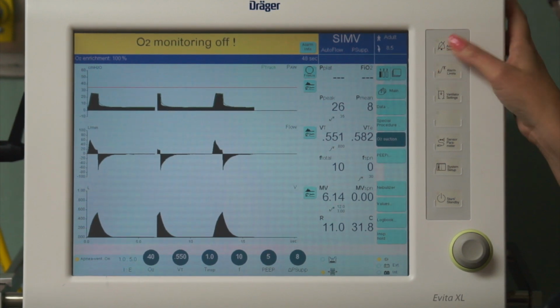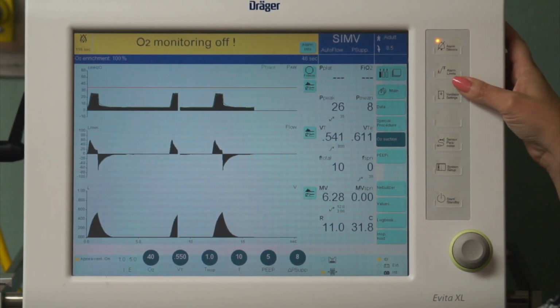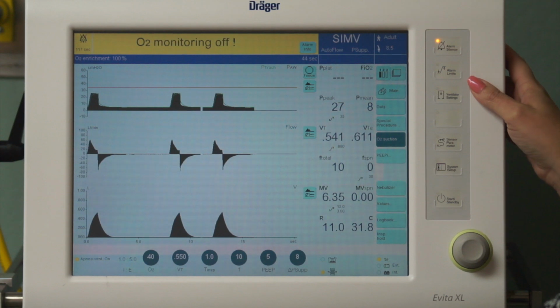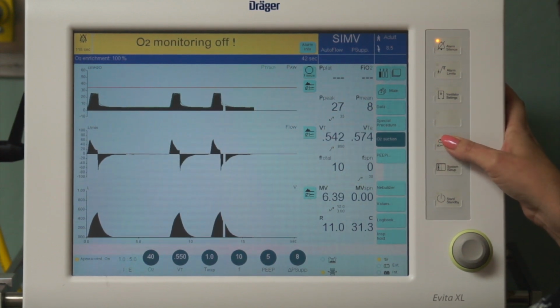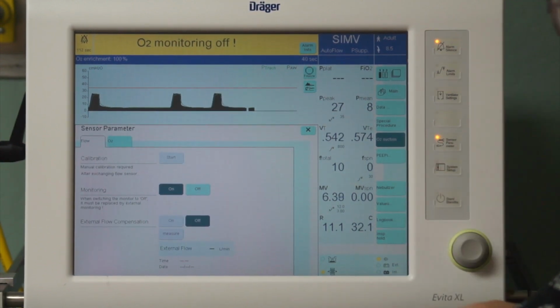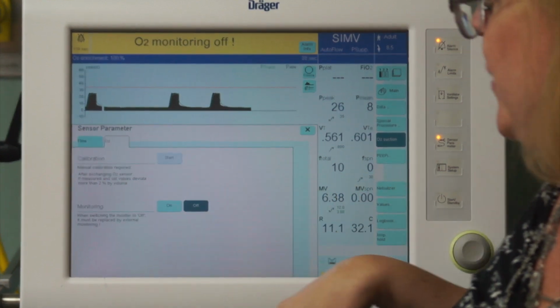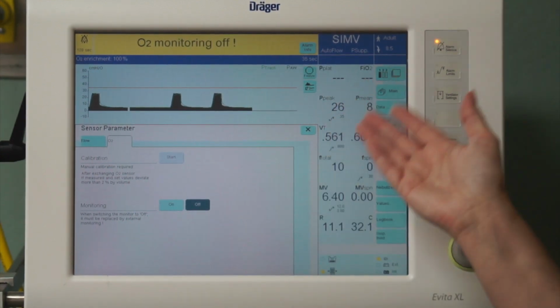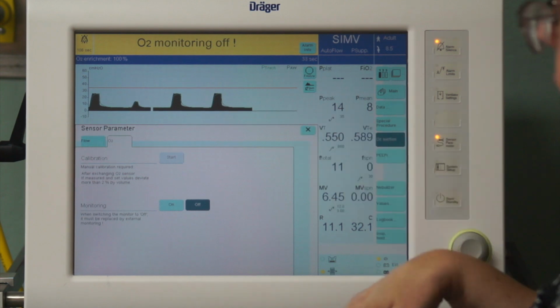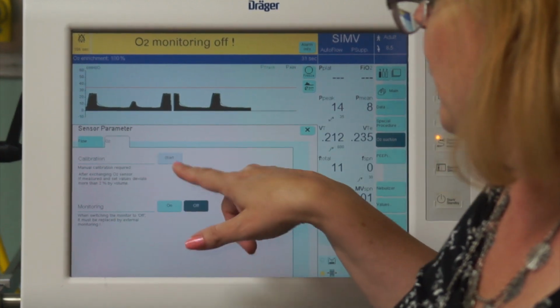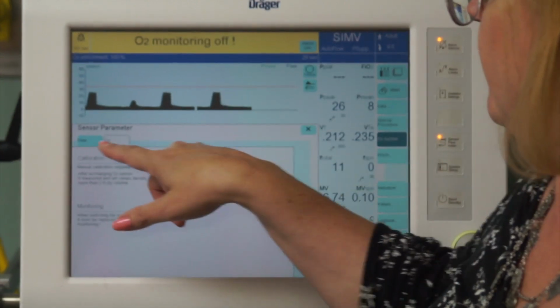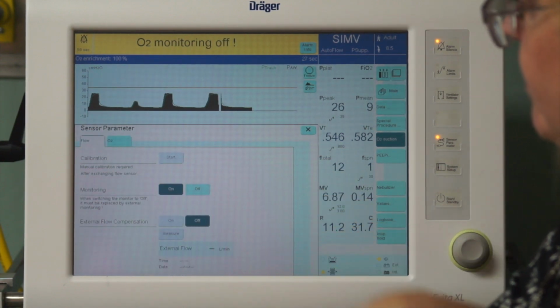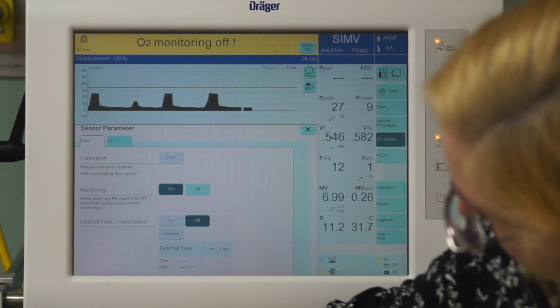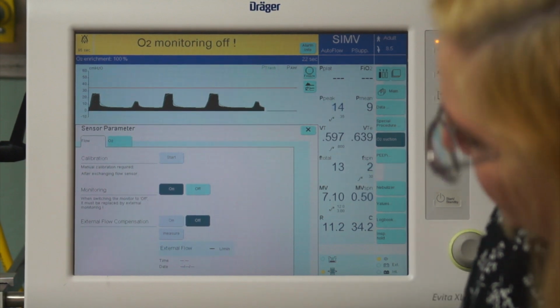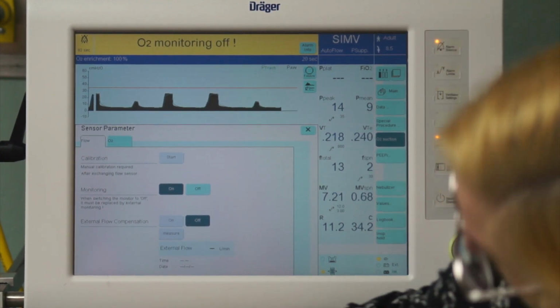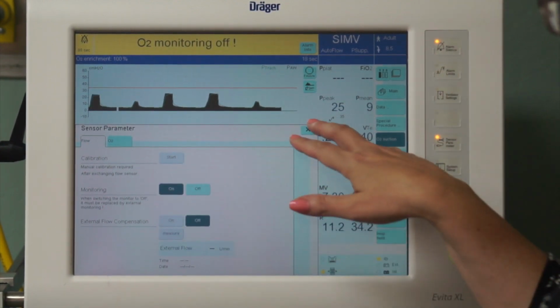So, alarm limits we went over, alarm silence, just like it sounds, is right there. Sensor parameter. This is for our O2 sensor. Currently now we have it off because we're using only room air here in the lab. So that's how we would do calibration and monitoring. Flow sensor, that's something we'll go over in an additional series, and that's our flow sensor right there, and we would calibrate that.